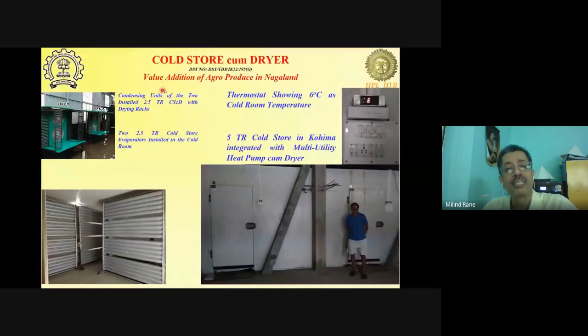Now we have deployed some of our technology for a cold store cum dryer. In this case, the cold store is maintained at about 6 degrees centigrade. This was deployed in Nagaland, to preserve the leftovers from the local vegetable market at the end of the day. And then the heat of the condenser was recovered to dry the produce, using the condenser heat recovery drying operation. And in order to avoid a backup genset and other things, we had built in an inbuilt storage. So even up to 4 hours, if the electricity is not available, the cooling effect will be supplied through the ice bank tank, which was deployed inside.